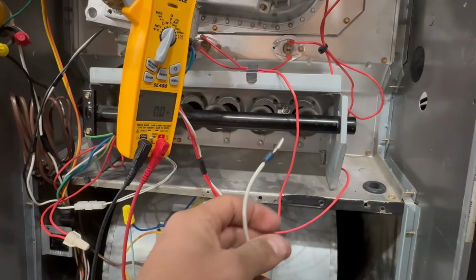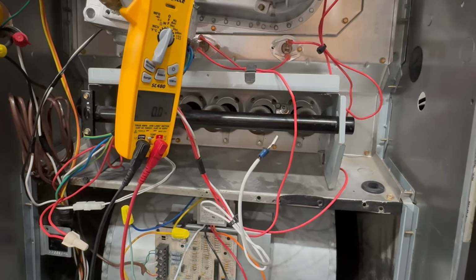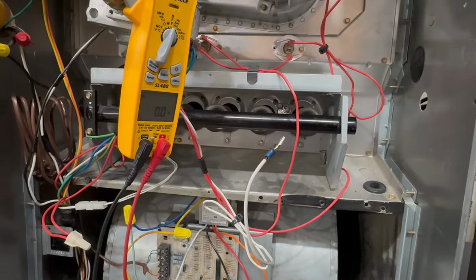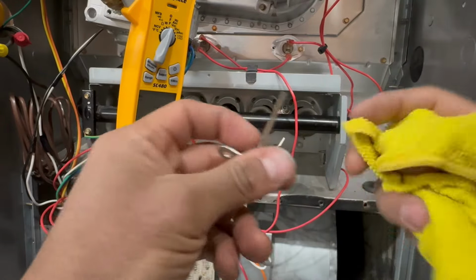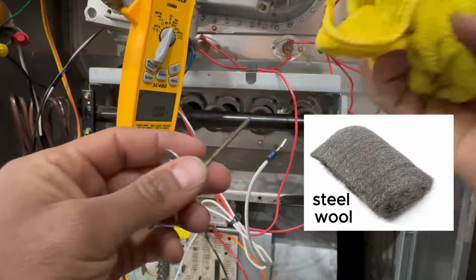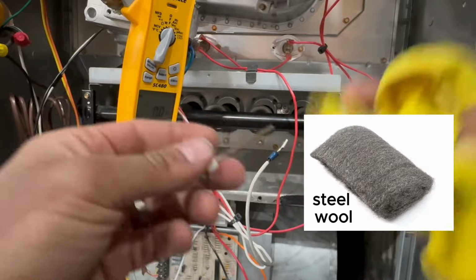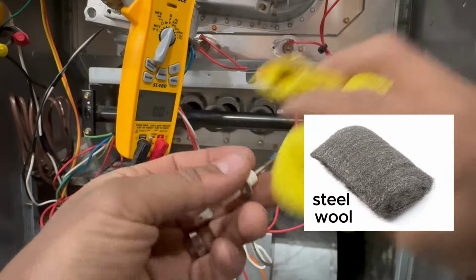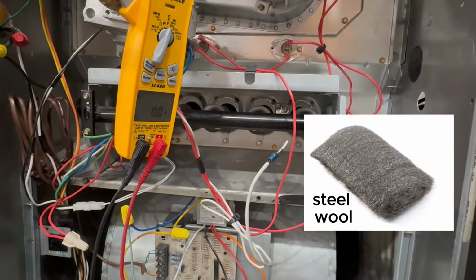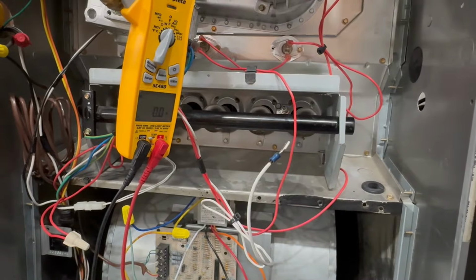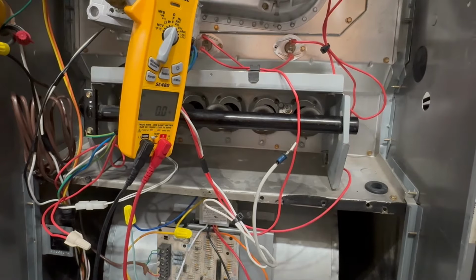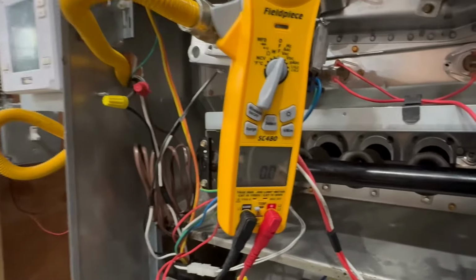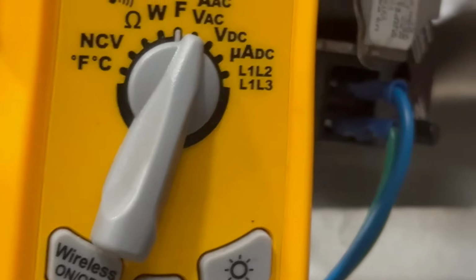So, with steel wool, right? I don't have steel wool right now, but you would simply take out the flame sensor and get the steel wool. This is just a rag, not steel wool, but just to give you an example, you just clean it, okay? Another way to know if your flame sensor is working properly is to check microamps. You have to have this symbol, and I'm going to show you guys how to check it.